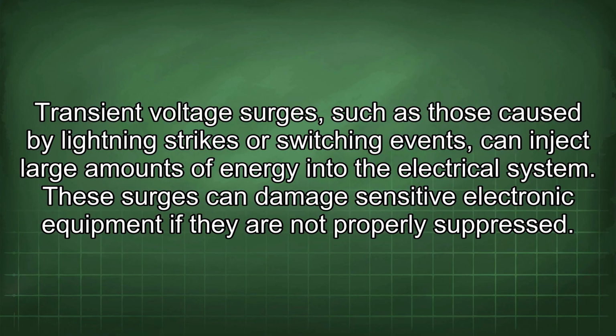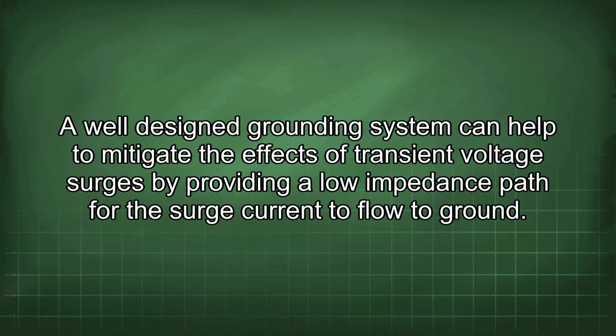Transient voltage surges, such as those caused by lightning strikes or switching events, can inject large amounts of energy into the electrical system. These surges can damage sensitive electronic equipment if they are not properly suppressed. A well-designed grounding system can help to mitigate the effects of transient voltage surges by providing a low impedance path for the surge current to flow to ground.